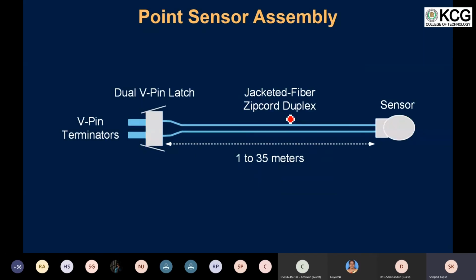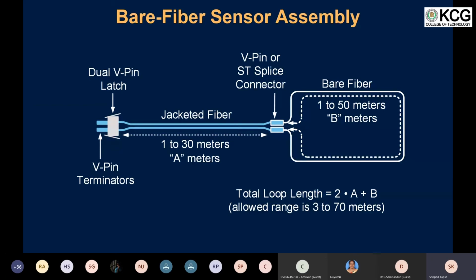So just to visualize, a sensor can be located as far as about 35 meters from the relay. This is typically required in any switchboard, because in a switchboard you would have a separate compartment where your control equipment is mounted and a separate compartment where your breaker is mounted. So you can place those up to 35 meters. If the arc flash hazard were to happen in the bus bar compartment itself, then you have a larger area to cover. To cover those kinds of places, we use bare fiber sensors, which are wrapped around the bus bar of the switchboard, and any arc flash that occurs in this bus bar can be detected as light through this sensor.